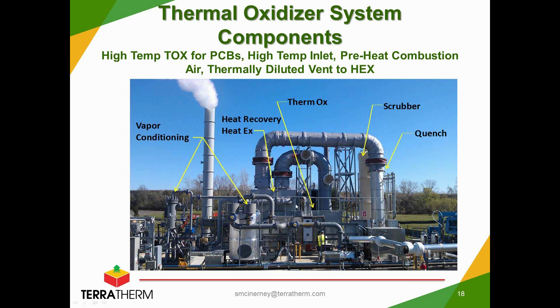The heat exchanger here, the materials of construction were such that the operating limit of that unit was approximately 1,800 or 1,900 degrees Fahrenheit. The vapors exiting the chamber here were closer to 2,300 degrees Fahrenheit. So some of these breather vents that you see that I'm pointing at are there so that under induced draft we could breathe in some ambient air and thermally dilute that exhaust temperature and get it down to or below the operational limits of the heat exchanger here, so we wouldn't overheat and damage that unit.